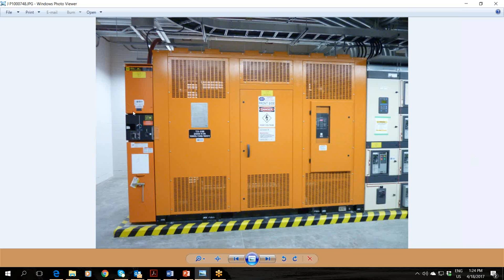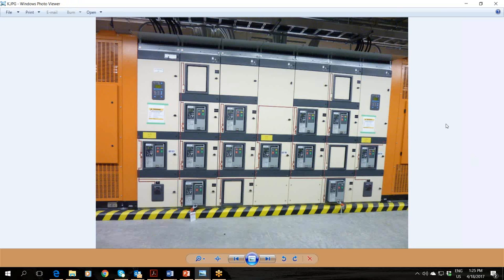It's the other half of that 15 kV switchgear lineup. You get to a different room, and you have a separate 15 kV load break just for isolation of this transformer. This is a cast coil dry type transformer, and we've close coupled from this switch into the transformer busing, and out of the transformer busing, close coupled to the 600 volt switchgear lineup. I know in the States typical is 480. In Canada, we're typically 600 volt for our low voltage switchgear class. We also have 208/120, which I know is common through the States and Canada. So that's just one of our switchgear lineups. You can see we've got a main-tie-main configuration here on the secondary, as well as the main-tie-main that we saw on the primary, giving us lots of options for that complex radial supply. And we do have an automatic transfer system for this main-tie-main arrangement.